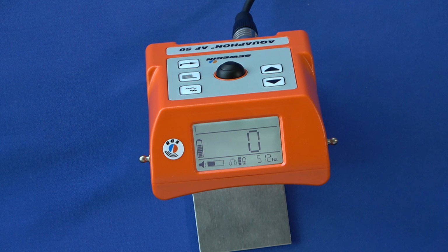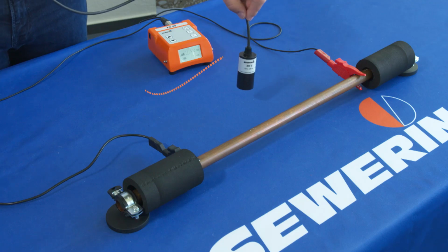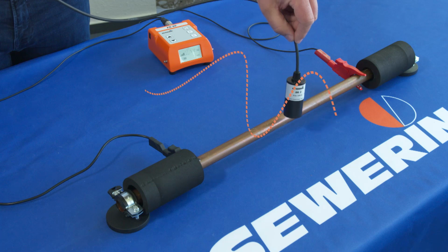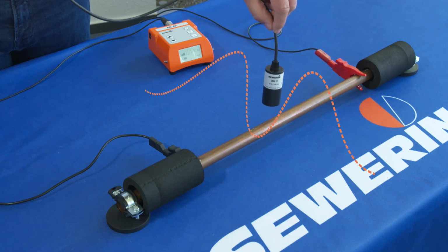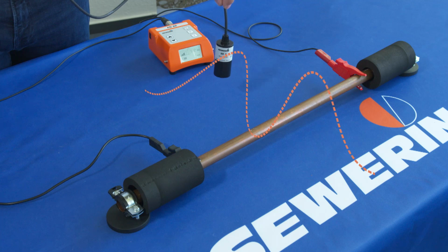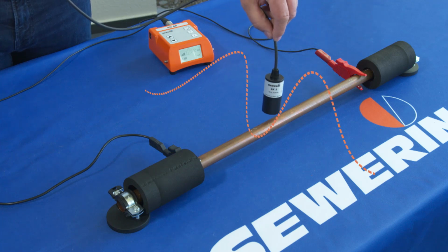The minimum method is suitable for pinpointing or tracking the pipe. The signal rises very strongly and becomes minimal directly above the line. To do this, move the search coil SK3 vertically over the pipe.